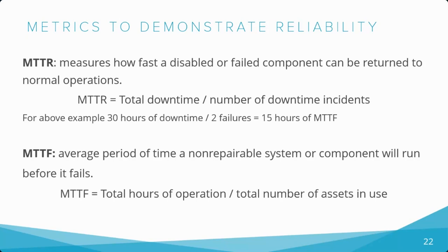MTTF, mean time to failure. This is the average period of time a non-repairable system or component will run before it fails. This is only used for systems or parts that can't or aren't going to be repaired. It's more likely to apply to a part such as light bulbs that would be replaced rather than repaired. It's calculated by adding the total operating time before failure of several light bulbs and dividing the total by the number of light bulbs being assessed.